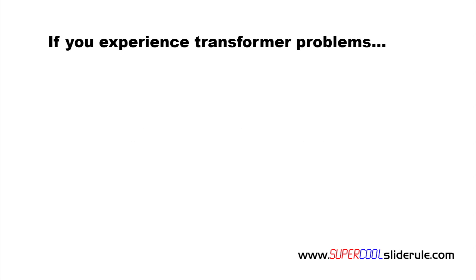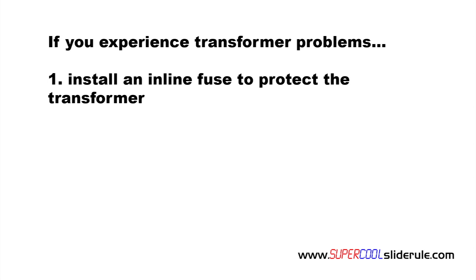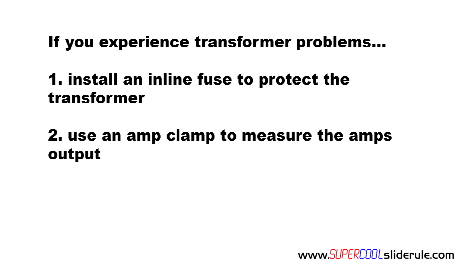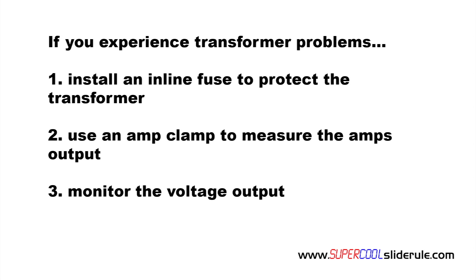If you are experiencing transformer problems, first install an inline fuse to protect the transformer. Next, you can use an amp clamp to measure the amp output of the transformer to ensure that it is not being overworked. And the third thing you can do is monitor the voltage output.